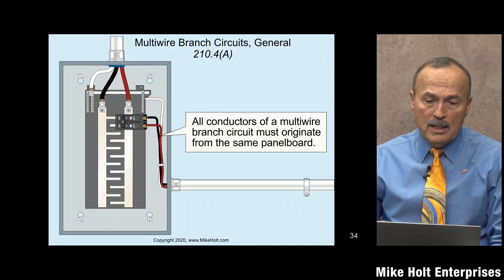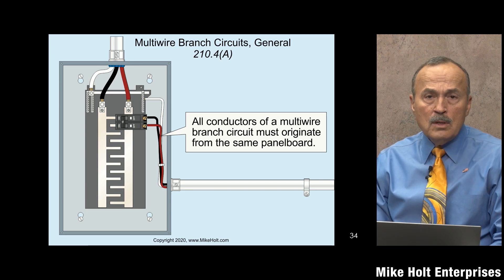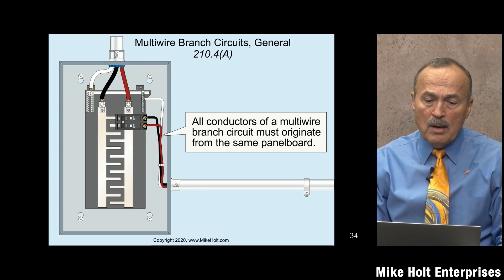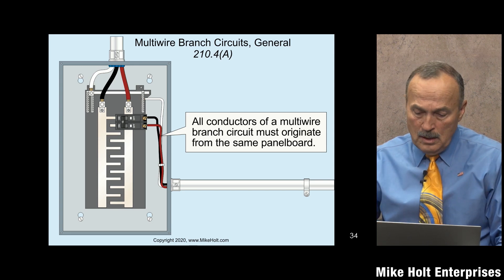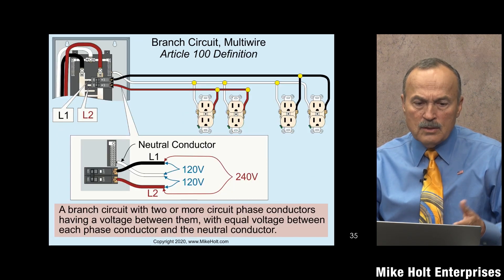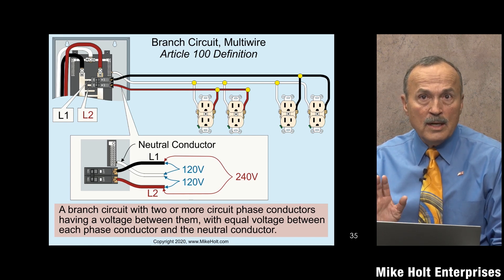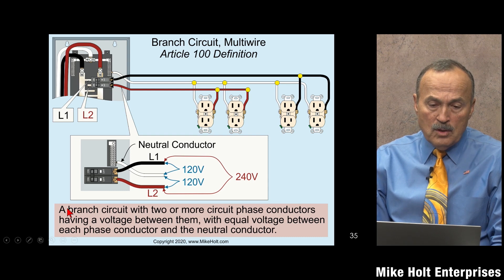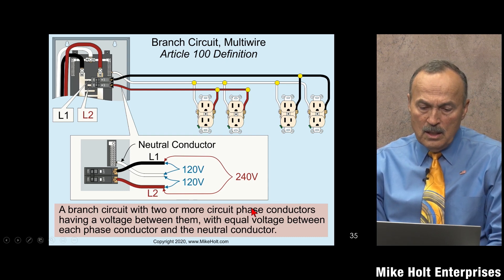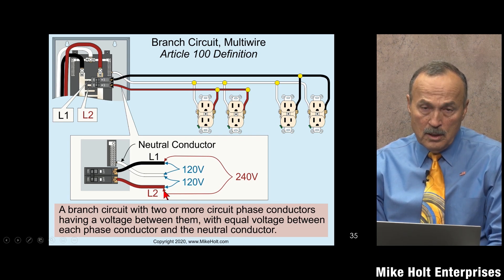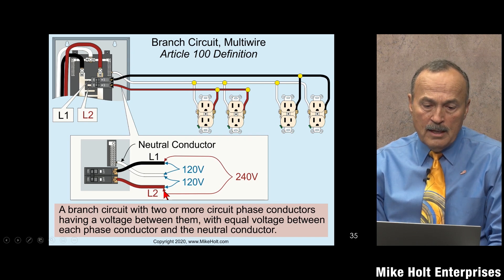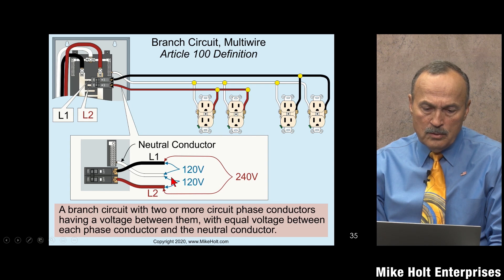NEC 210.4 deals with multi-wire branch circuits. The rule in 210.4A is that all conductors of a multi-wire branch circuit must originate from the same panel board. Here's a graphic of the definition of a multi-wire branch circuit for single phase: it is a branch circuit with two or more phase conductors having a voltage between them — line one and line two — with 120 volts from each line to neutral.